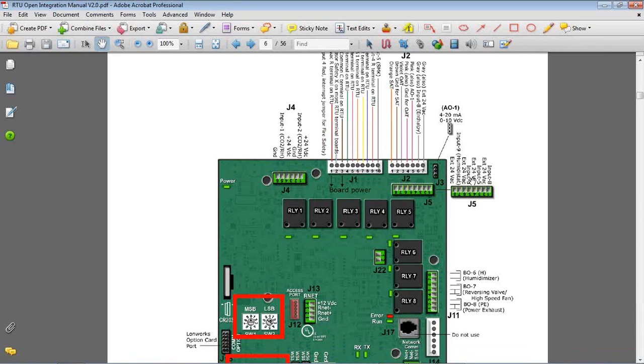Okay, so if I, for instance, wanted to wire in a humidity sensor, I would have to wire it to one of these inputs. Then I would have to tell the controller, you have a humidity sensor wired into this specific input, so it knows where to look for its value. Okay, all the logic to control with humidity or CO2 is all standard on the rooftop controller. You just need to tell it where that actual sensor is wired in so it knows where to look.